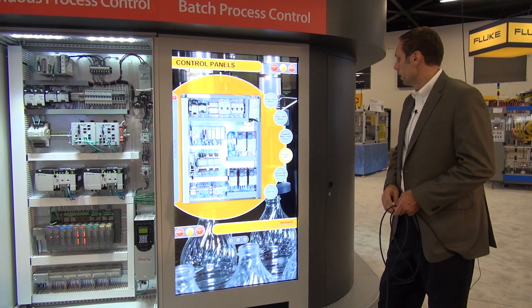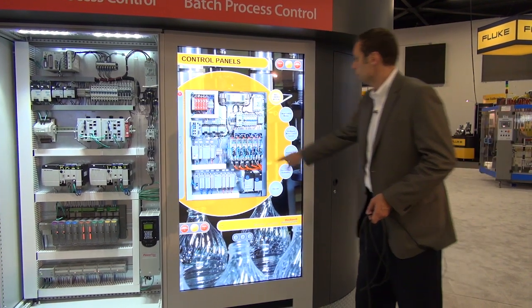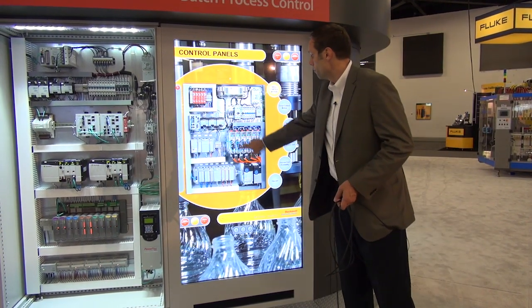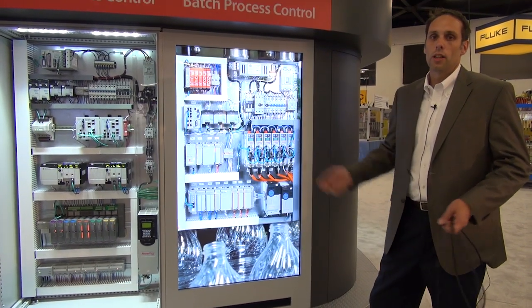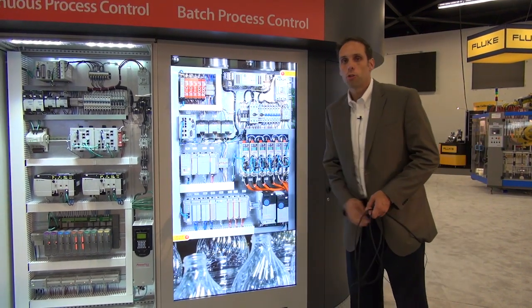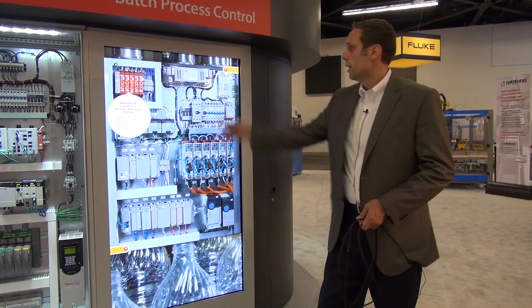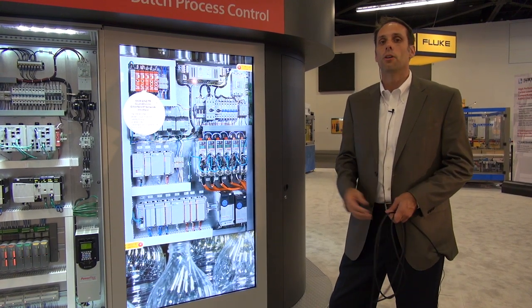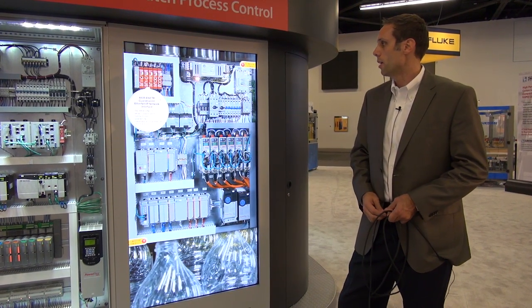The other key system I want to talk through is our small motion control system. Here we're talking about a lot of new safety-type applications. Specifically, we've now launched the PowerFlex 527 family, which gives us STO motion in an AC drive format. The Kinetix 5500 is also now enabled with network power safety when used with the GuardLogix processor, giving us both STO motion and STO safety in a modular small servo platform. For small and simple safety applications, we're now introducing the 440R Ethernet adapter for our safety relays, which allows us to add safety in a premier integration model to any mid-range system with CompactLogix in many of our safety applications.